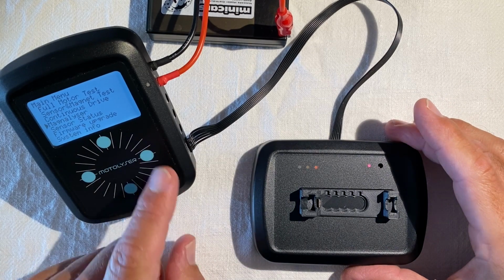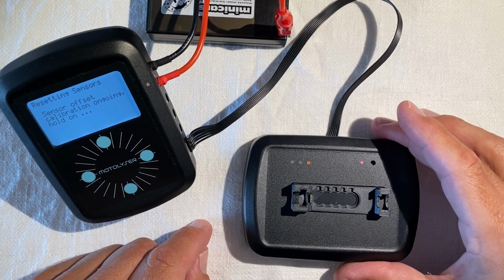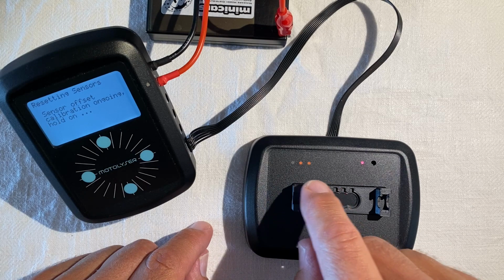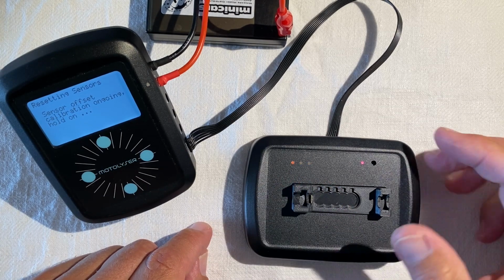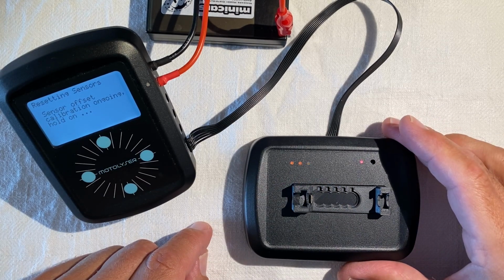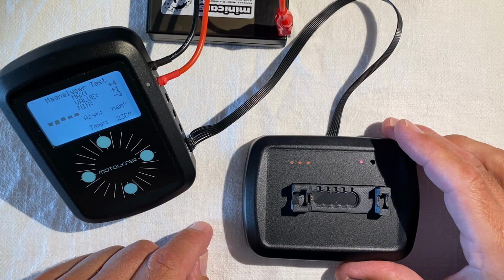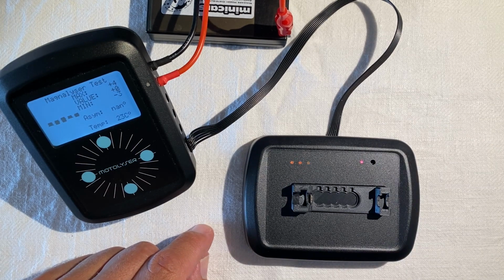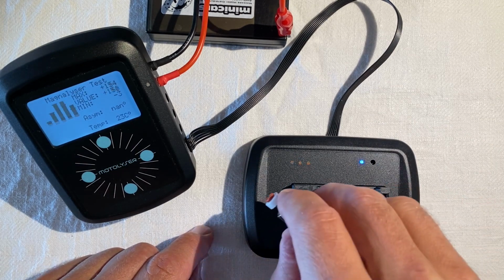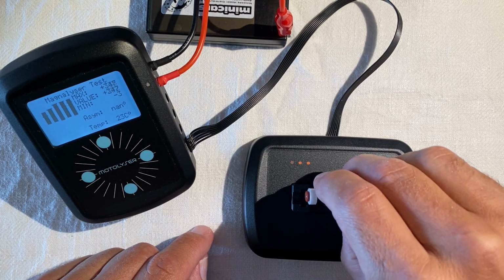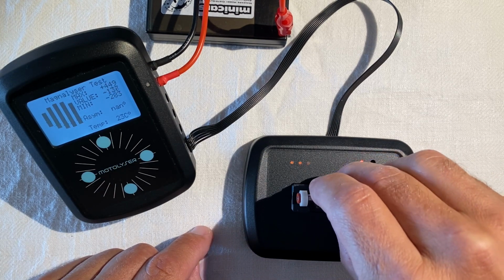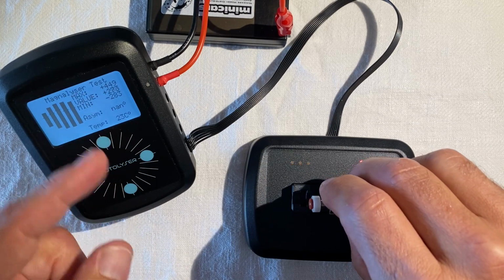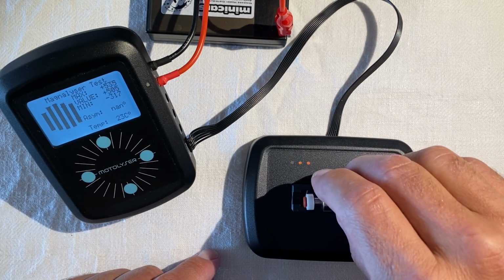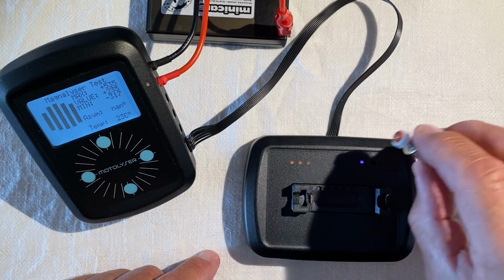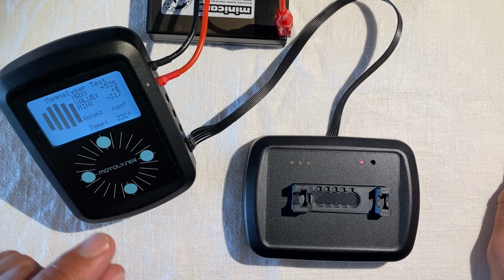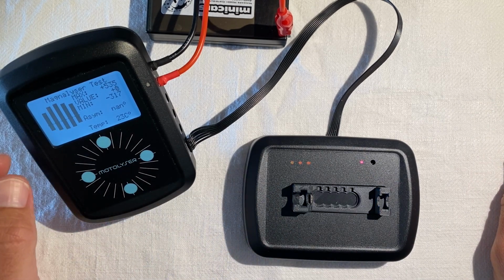So the first thing that happens now when we start the Magnalyser is that it runs through all the different sensors and calibrates the bias offset. And now we're good to go. We can bring out our rotor again just to make sure that it responds. As you can see, we get values on these bars and the mean and max value of the rotor field strength. So now it's hooked up. Let's go for initial calibration.